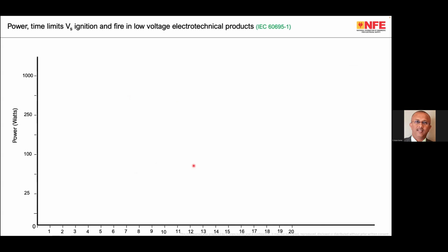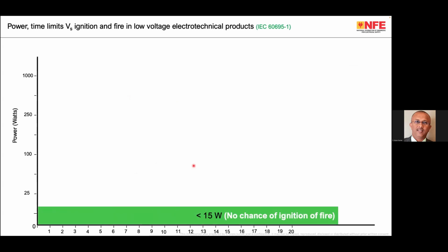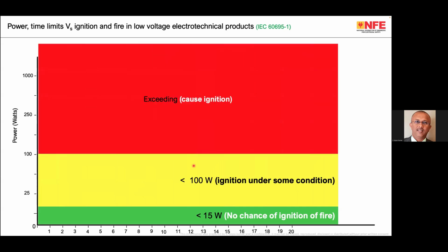One of the concepts considered in the standard is the heat produced because of a fault. If the heat produced is less than 15 watts, even for a longer duration, it is not supposed to ignite a fire. No chance of ignition of fire if the heat produced is less than 15 watts. If the heat produced is between 15 and 100 watts, ignition can happen under certain conditions. And if the heat produced is more than 100 watts, of course, the equipment itself will catch fire. The equipment itself will start burning.